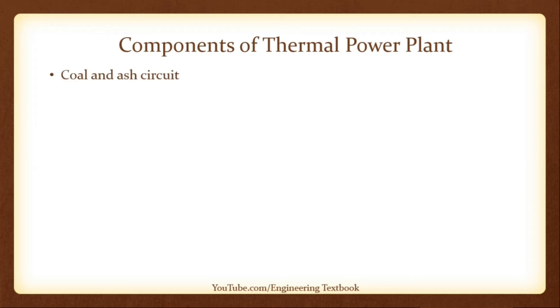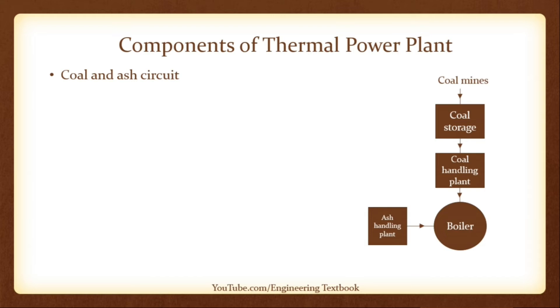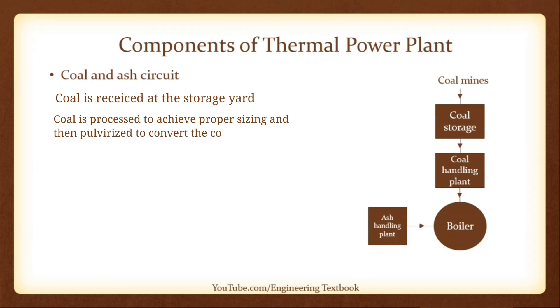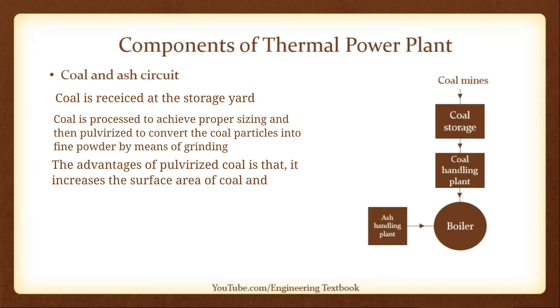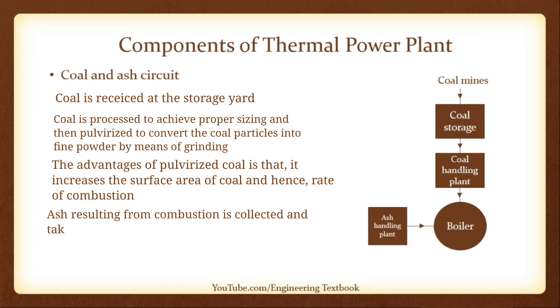Coal and Ash Circuit. Here is the diagram of the coal and ash circuit. Coal is received at the storage yard, processed to achieve proper sizing, and then pulverized to convert coal particles into fine powder by means of grinding. The advantage of pulverized coal is that it increases the surface area of coal and hence the rate of combustion. Ash resulting from combustion is collected and taken to the ash storage yard through the ash handling system.